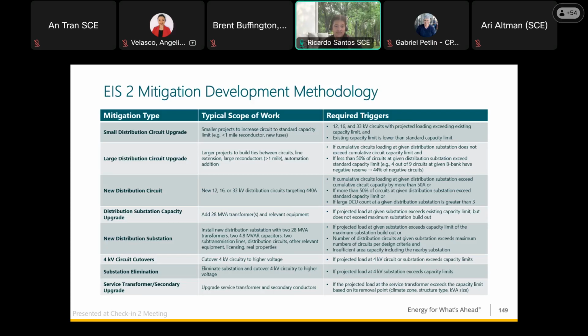So for example, for a new distribution circuit to actually be proposed by the script, either of the following required triggers would need to occur for the script to recommend a new circuit. So looking at the right column, if cumulative circuit loading at a given distribution sub exceeds cumulative circuit capacity by more than 50 amps, or if more than 50% of the circuits at a given distribution sub exceed standard capacity limit, or if a large distribution circuit upgrade count at a given substation is greater than 3. So again, because this is an OR statement, any of these triggers can happen for a new circuit to be proposed.